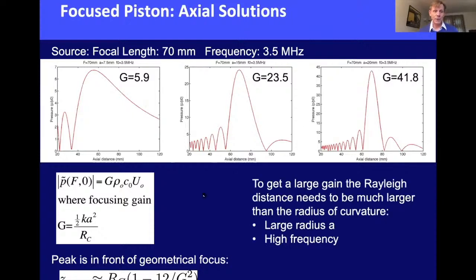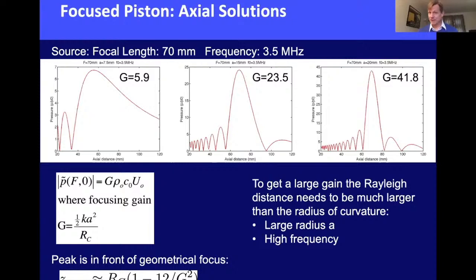For a highly focused transducer, the gain should be large. The radius of curvature is generally fixed by the treatment depth. The two design parameters are frequency (which changes k) and aperture a. To maximize gain, you want the Rayleigh distance much larger than the radius of curvature — the largest aperture possible and the highest frequency that still allows penetration to the target depth.